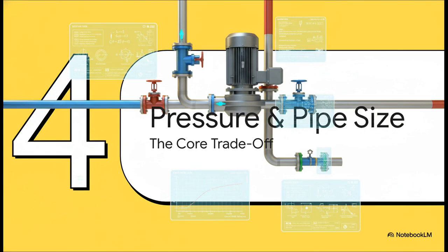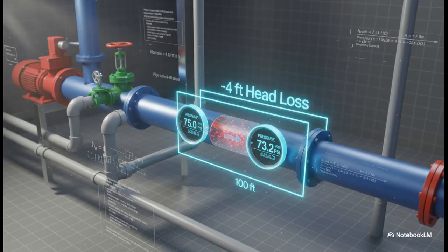And that leads us to the final piece of the puzzle, and probably the biggest balancing act of them all: managing pressure loss. This is where things get really interesting, because this factor directly connects the pump you need to the size of the pipes. As water flows, it naturally loses pressure because of friction with the pipe walls. Engineers have a special way of measuring this. They call it feet of head. It's a bit of a weird unit, I know, but just think of it as a way to talk about pressure. A really common target, kind of a rule of thumb for designers, is to aim for a loss of about 4 feet of head for every 100 feet of pipe.